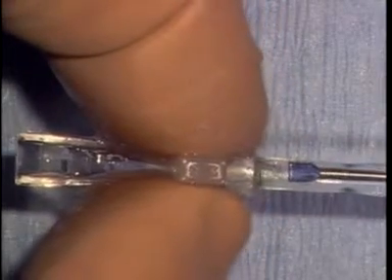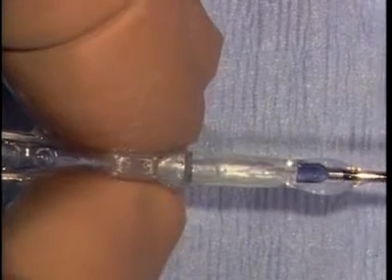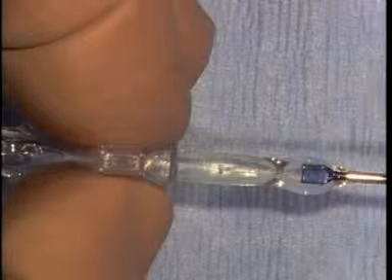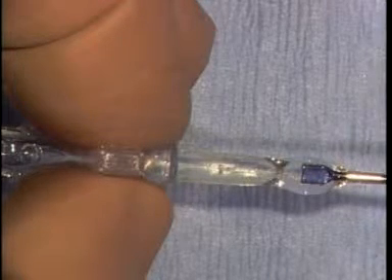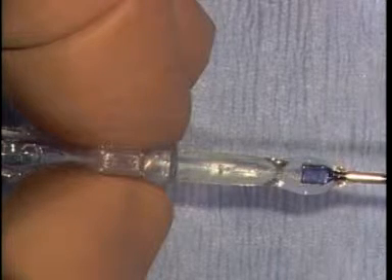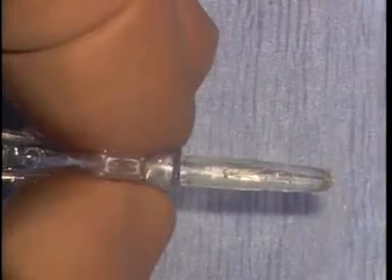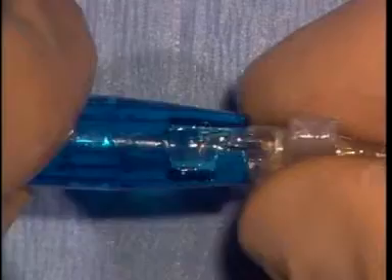Observe the lens positioning marks on either side of the Visian ICL optic to confirm alignment as you advance the ICL. Continue this process until the ICL is positioned within the cartridge so that its leading edge is adjacent to the end of the cartridge. Release the ICL and remove the forceps. Slide the cartridge into the front of the injector and snap lock the vertical tab into position.